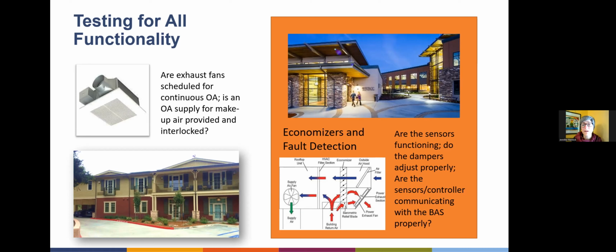Unfortunately, these economizers were known to the state of California to not really deliver the energy savings that the manufacturers had promised. And that had nothing to do with the manufacturers. It had a lot to do with how they were installed and how they were operated, with folks doing the installations not really realizing how to finish setting up the economizers if they were not factory integrated and already set up.